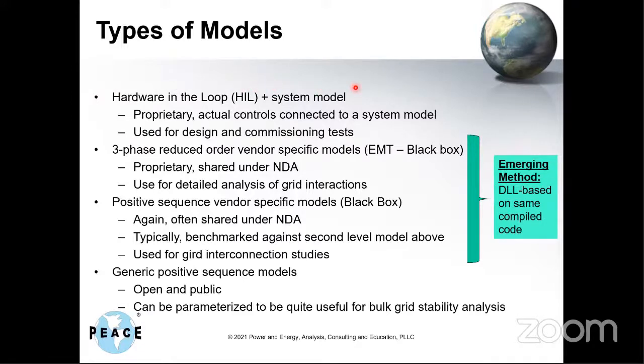At the highest level, the most sophisticated models are hardware-in-the-loop, and this has been done even for synchronous generation. I've worked with these at GE years ago. Basically you take the actual hardware, like the converter controls, and hook it up to a computer that simulates the grid. Then you can simulate faults and play all sorts of games, so you have hardware-in-the-loop plus a simulation of the grid. These are obviously proprietary. Utilities will sometimes work with a vendor to buy one and set it up in their own lab. There are entities that do this, so you can do really high-level design and commissioning tests with these things.